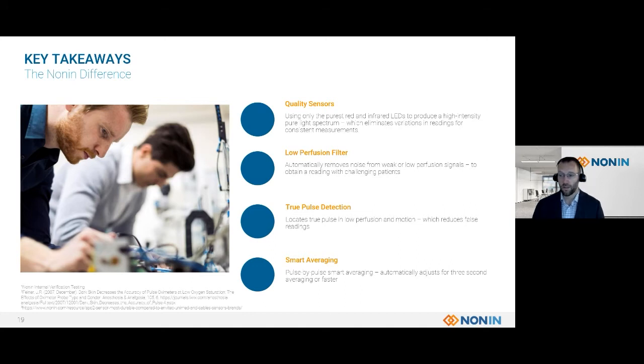We discussed earlier, Nonin's accuracy starts with the quality sensors. All pulse oximeters use red and infrared light to measure SpO2. Only the PureSat sensor technology uses the purest red and infrared light to produce high intensity light spectrums, which eliminates variability. The PureSat technology also offers low perfusion filters that provide a true and reliable reading cleared by the FDA. This filter automatically removes noise from the weak or low perfusion signals to obtain a reading even in challenging patients.